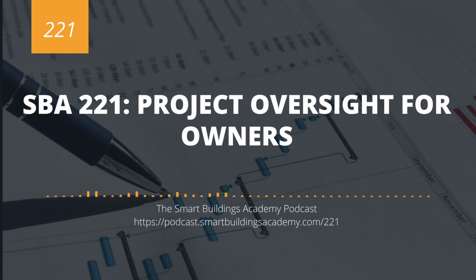Let's say that the business use case, it's a hospital, and your purpose of that hospital is to do operations, to do imaging, to do patient care, etc. Well, if you have an issue with airflow or pressurization or a visualization of data or test and balance, whatever the issue is, would you rather catch that prior to certificate of occupancy, or would you rather figure out that there's an airflow or humidity issue in the OR when someone's having open heart surgery? I know that's kind of a drastic example, but at the same time, we really need to get away from this belief that warranty is just an extension of the project that lets us kind of clean up everything. We really should have projects closed out prior to project closeout.